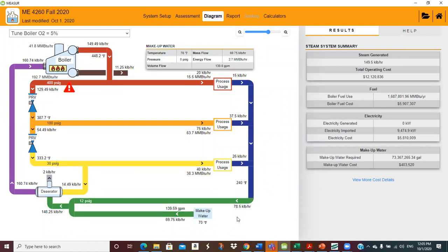And again, we said this before, that MEASUR doesn't have the ability, it's not set up to put in this condensate, but this is receiving the 30-pound header condensate, and so the assumption would be that we have 30 pounds here at 240, and it's coming back, and the information given is that it's going into a tank here, which is atmospheric pressure, and so if it's above 212 or so, it's going to generate flash steam.